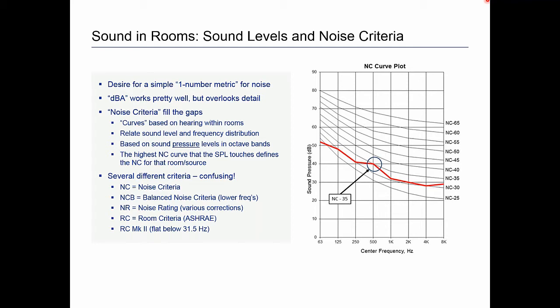So we use noise criteria curves, often called NC ratings. These curves are based on how people hear sound in rooms and relate sound level to frequency distribution. We take the sound pressure level in octave bands and map it on a chart against these curves; wherever the spectrum touches the highest-numbered curve, that's the NC level. Unfortunately there are several different noise criteria systems: noise criteria (NC), balanced noise criteria, noise rating, room criteria, and room criteria mark two. The most common two are NC curves and the room criteria, which ASHRAE has recommended.